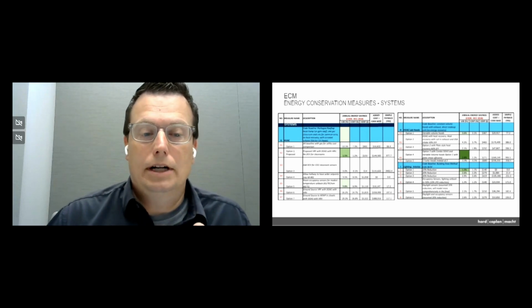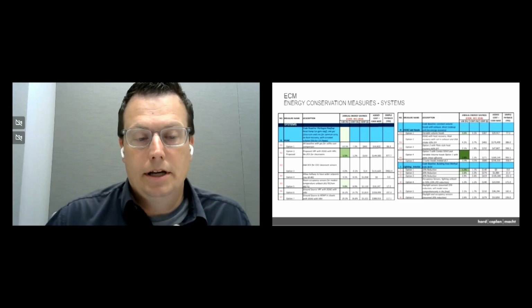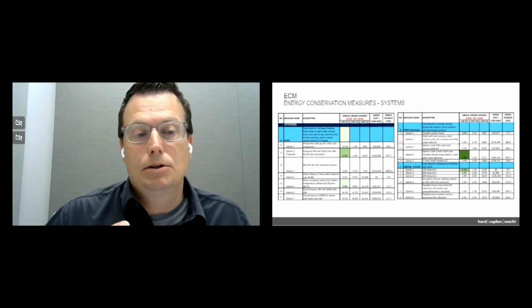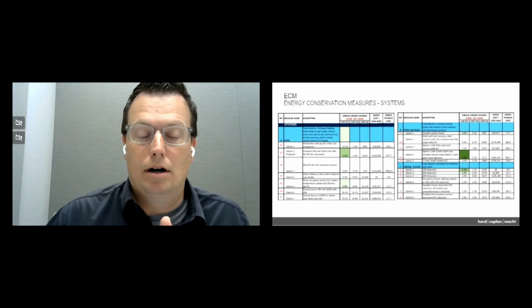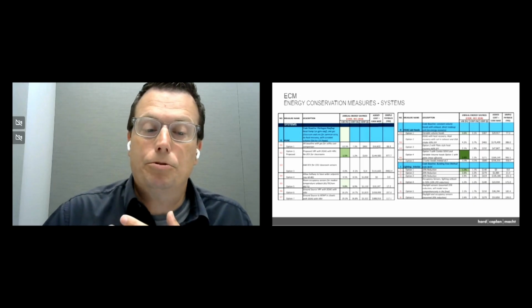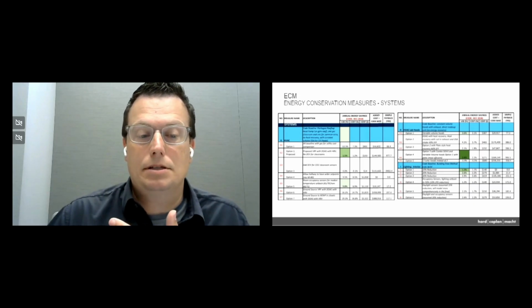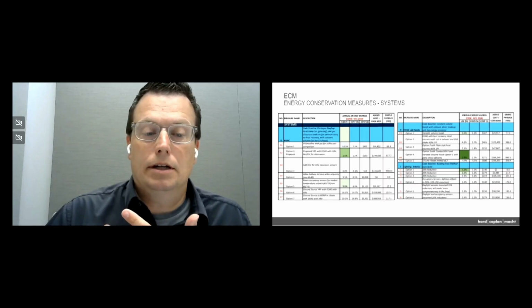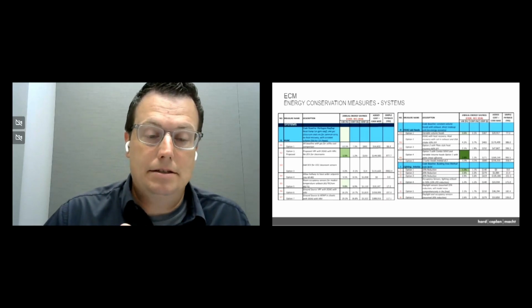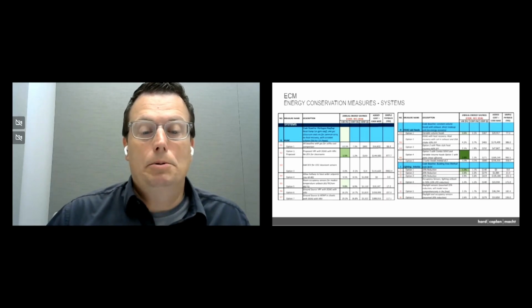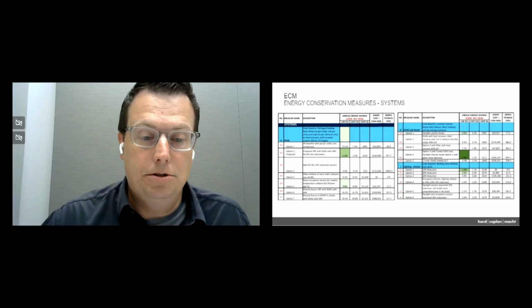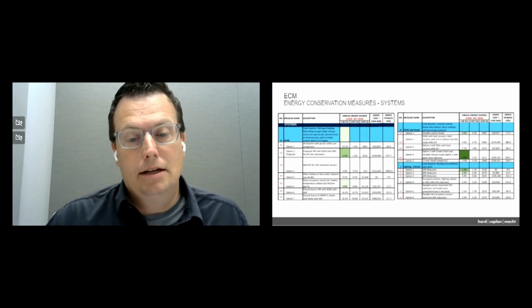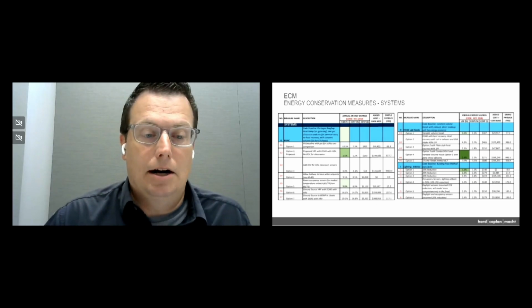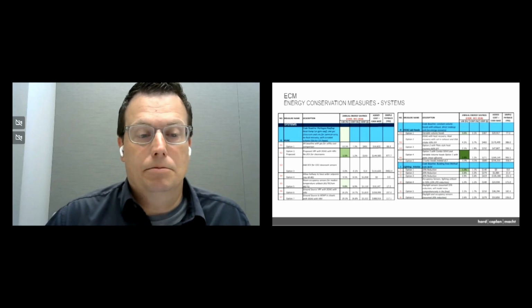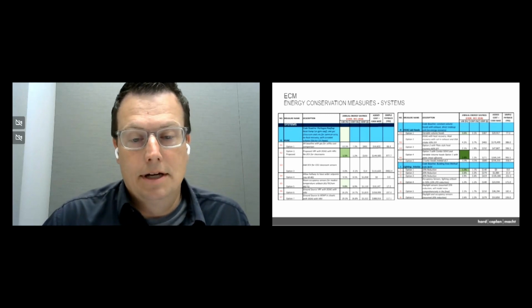We settled on a VRF system with heat recovery for the classrooms, which had modest energy savings overall. What we found was that through control systems like occupancy sensors and daylight sensors for lighting control, we were able to reduce energy use on the control side to offset the more baseline VRF system.